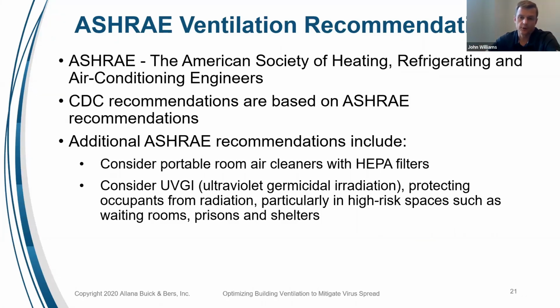And in addition to all those, ASHRAE had a couple other things that were not picked up by the CDC that ASHRAE recommends. One of those is cleaning with portable HEPA air filters. As I mentioned before, even the best HEPA filters only go down to about 0.3 microns, and our coronavirus is about 0.1 microns. So we can't be guaranteed that the HEPA filters will capture the coronavirus, but we can hope that, like a bug on the front of a car, the coronavirus is going to run into the HEPA filter and be captured.